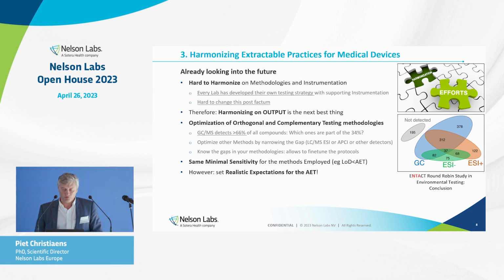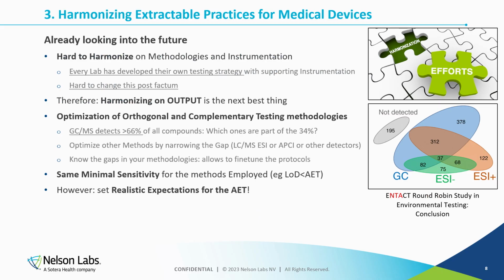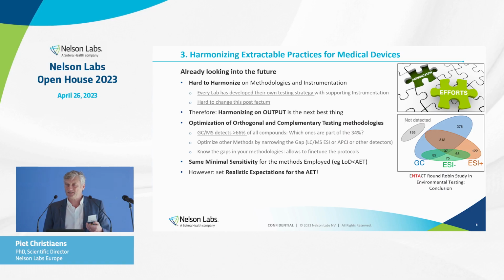And here, for instance, I would like to refer to a study that has been done in the environmental world. It was some kind of round-robin testing, where they had, I think, 1,200 pollutants, and it was, like I said, a round-robin. It was sent to different labs, and they saw that 66% of those compounds were detected with GCMS. So that's a good place to start, because you're able to detect about 66% of those compounds. My gut feeling, based upon what I see passing in our lab, is that it's more or less the same. That about 2/3 of the compounds will be detected with GCMS.